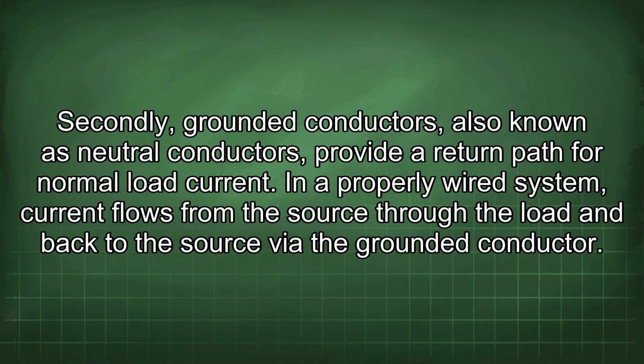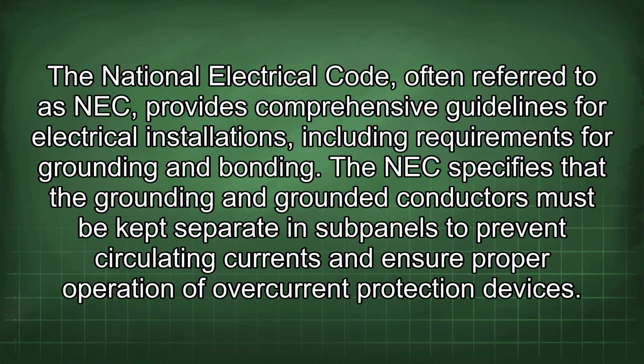In a properly wired system, current flows from the source through the load and back to the source via the grounded conductor. The National Electrical Code, often referred to as NEC, provides comprehensive guidelines for electrical installations, including requirements for grounding and bonding. The NEC specifies that the grounding and grounded conductors must be kept separate in subpanels to prevent circulating currents and ensure proper operation of overcurrent protection devices.